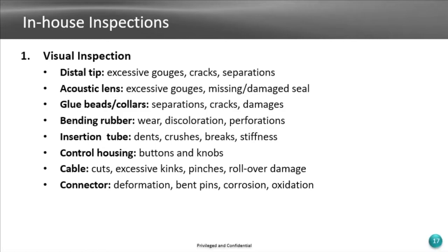And they're going to say, wait a minute, this has to go in. So they're going to jam it in and lock it. Now those bent pins, those damaged pins on that probe, are going to damage the connector board on the machine. So now you have two problems - a damaged probe and a damaged machine.